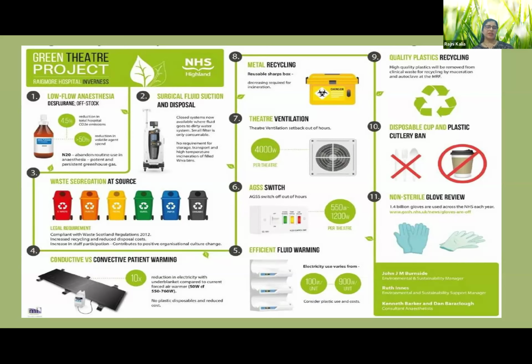Conductive versus convective patient warming: comparing the fluid warm under blanket of the patient and the Bair Huggers, there was around a 10 times energy difference in the under blanket as compared to the disposables that were used in the forced air warmers. The other thing initiated was efficient fluid warming, which decreased the plastic use and the cost, and definitely the electricity, from 900 watts per unit that was used with the fluid warmer to 100 watts with this efficient fluid warming.